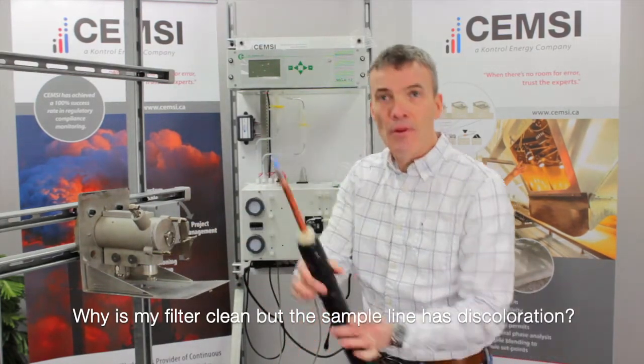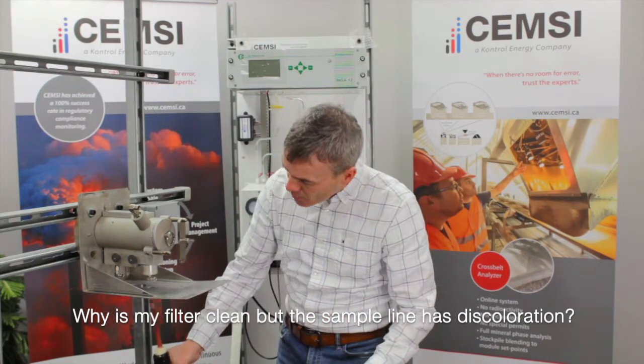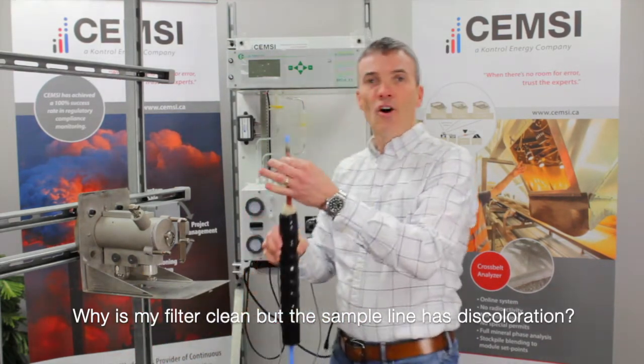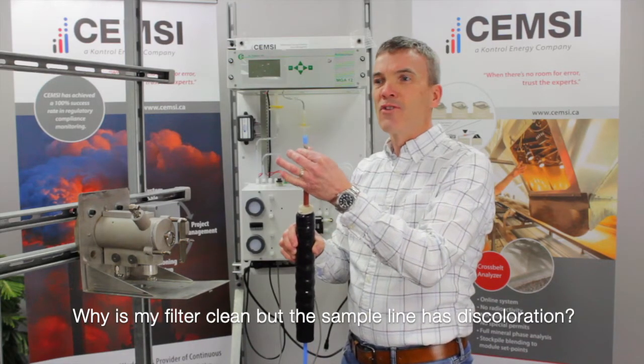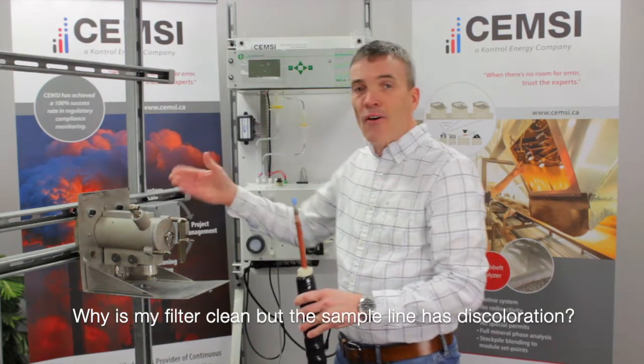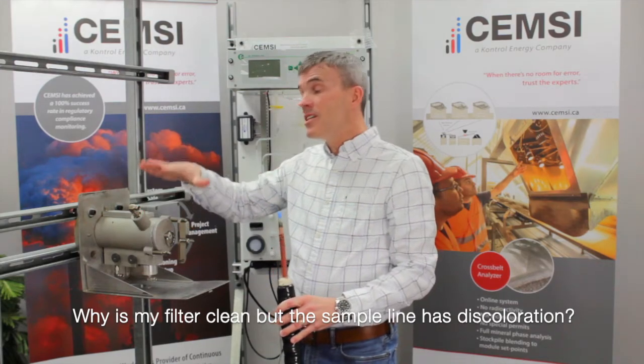But then they look at their sample line, an example of a sample line that connects onto the unit. It's all discolored inside. Brown, starting to go black with the hydrocarbon inside. How can this be? What's the problem with my filter? There's actually nothing wrong with your filter.